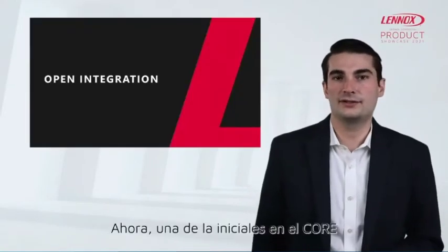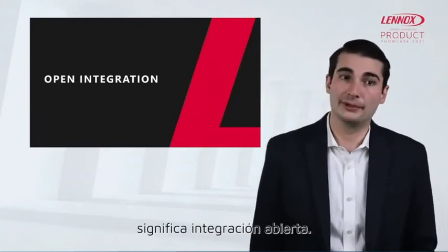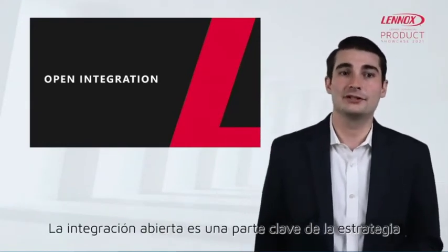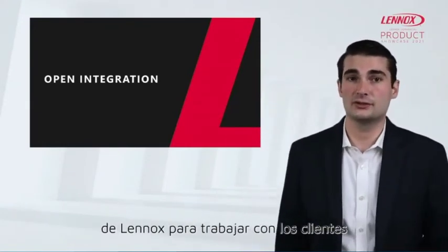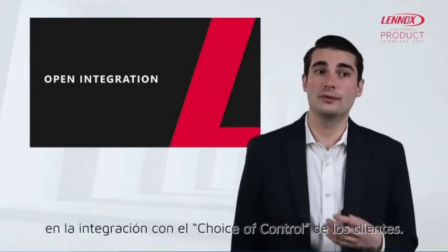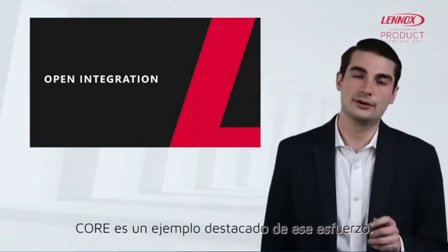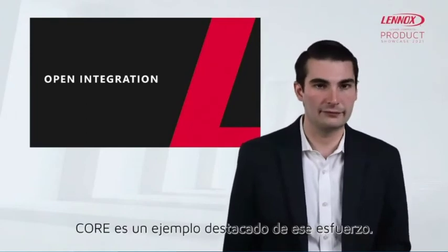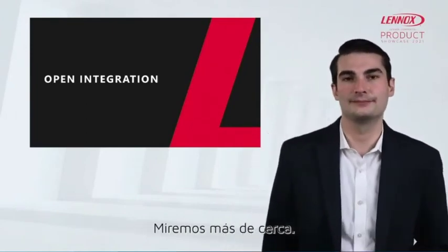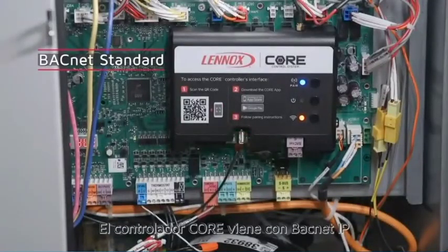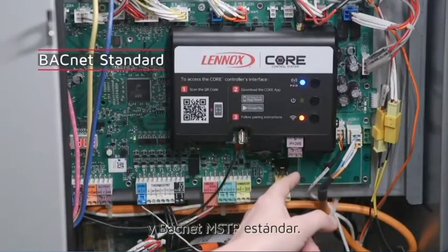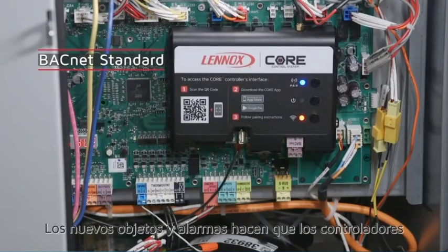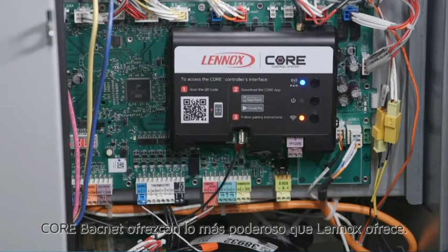Now, one of the letters in CORE stands for open integration. Open integration is a key part of Lennox's strategy to work with customers on integrating with the customer's choice of controls. CORE is a leading example of that effort. Let's take a closer look. The Lennox CORE unit controller comes with both BACnet IP and BACnet MSTP standard. New objects and alarms make the CORE unit controller's BACnet offering the most powerful Lennox has to offer.